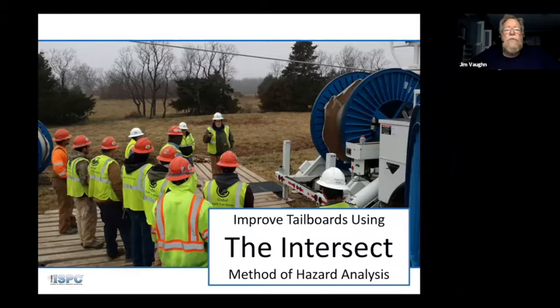We had a metal clad switchgear contact that occurred. When I went to investigate, nobody was killed. The guy got some burns on his hands and some burns on his face. This was before the FR and face shield days. They were replacing the feeders leaving 4 kV switchgear that were going out into a big mine processing facility.